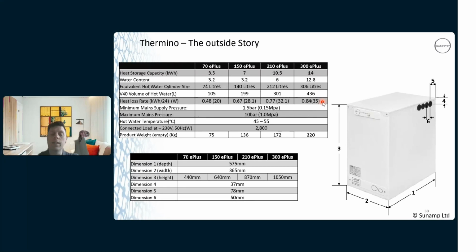Somebody may ask you, how long is my heat battery going to last if I have it fully charged and don't use it? What you would do is take your storage capacity, let's work on the 70, your storage capacity is 3.5, and you would divide that by your heat loss, 0.48, and that gives you your length of time in days before you're at 0%. So if everybody wants to do the calculation with me just now.